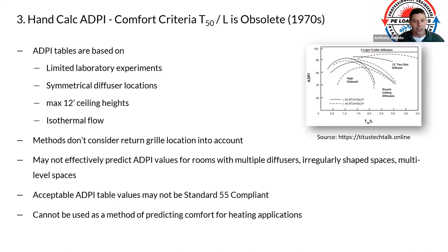It uses isothermal throw and symmetrical diffuser locations, and doesn't consider anything about return locations. People ask, what if your return is over here or there—how does it impact things? You kind of have to guess: I don't think it will impact much, or maybe it's short-circuiting here, but we never really had that information from these tables. Then matching the type of grill with these ADPI charts, the terminology used may not match what manufacturers give you, so you have to line things up.